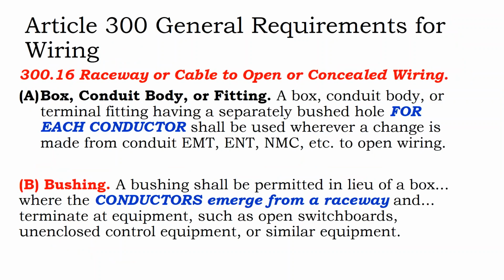So particularly for interior wire run retrofitting, where you have to drop a solar cable down a wall, you think, well, how am I going to retrofit conduit down a wall? It might be that you go for a higher end, $5 a foot cable, but you're also saving some money. Now you've turned what would be an impossible job into a possible job, which is the most important. But B, you're also not buying the EMT conduit and all the fittings you necessarily need. So there is some cost savings there that makes up for the higher cost of the cable. And there are installers who are big fans of internal wire runs who just use metal clad cable for their inside wiring because it's easier for their work process.